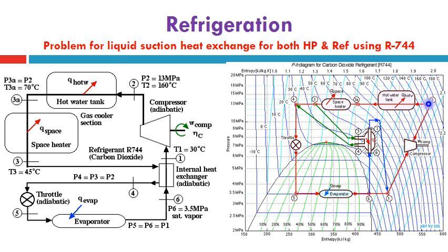iso-efficiency line, and we will locate points 2, 3a, 3, and 4 on the shown pressure of 13 megapascal. P2, P3, P4 are all on the line of 13 megapascal, which is located here, around 130 bar, a very large amount. So we should take into consideration that no condensation happens here, because this pressure is very high and higher than the critical point, which is the intersection point between the vapor saturation line and the liquid saturation line.